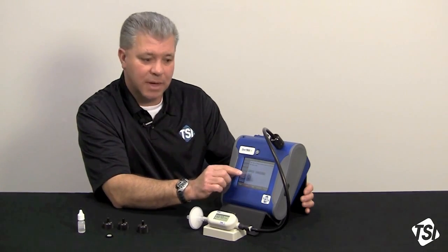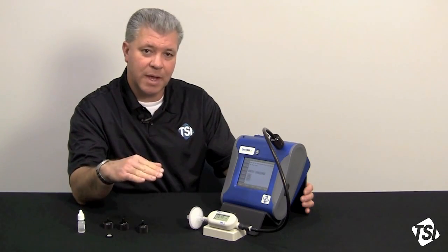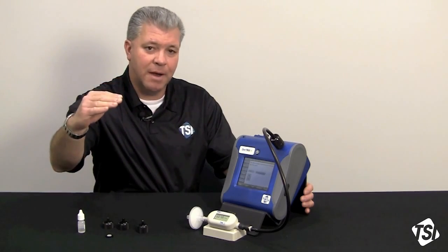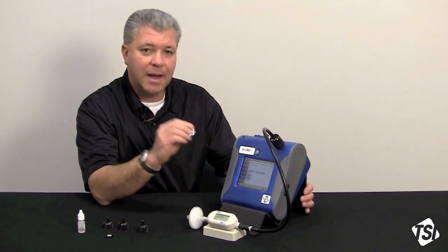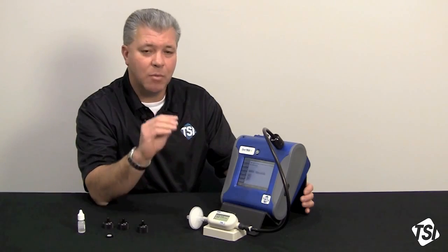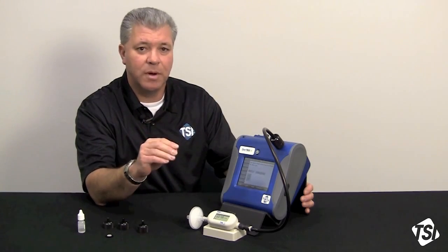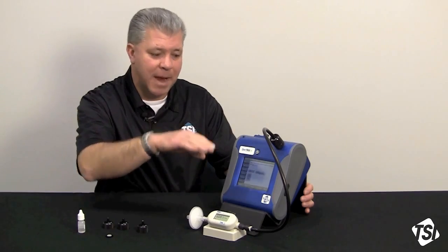What that amounts to is you can go from 0.5, its lowest setting, to 1.5, its highest setting on the span potentiometer. That in no way is equated to 0.5 liters and 1.5 liters of flow. It's simply the minimum span potentiometer setting and the maximum.